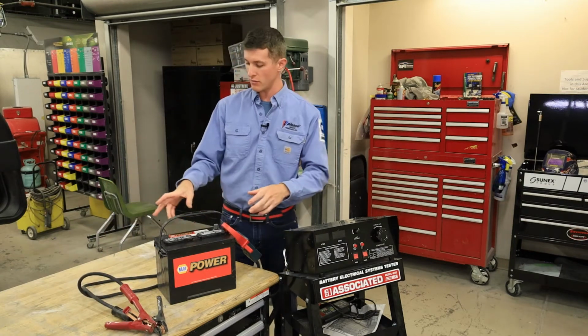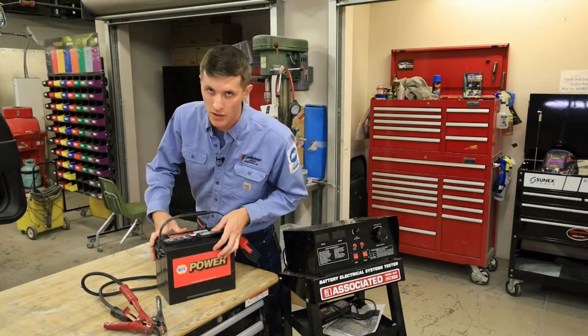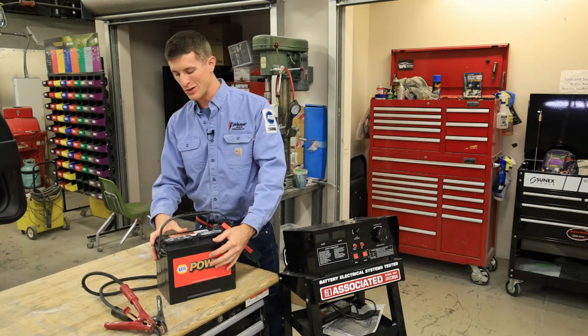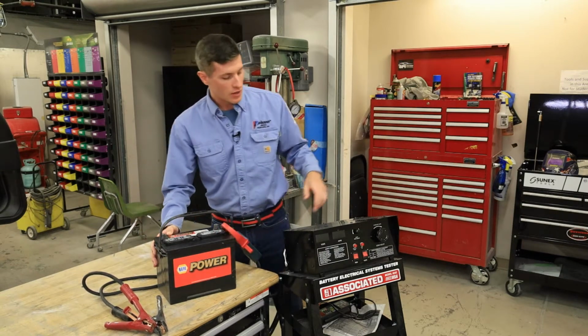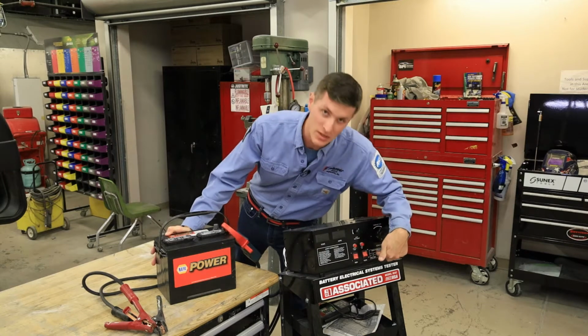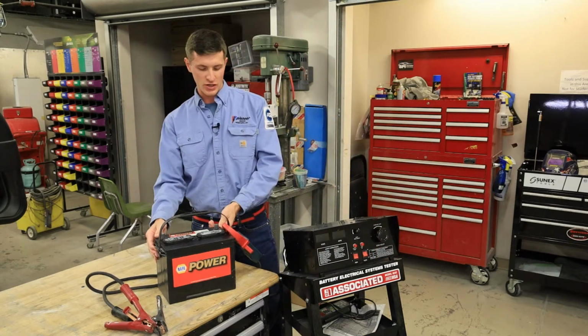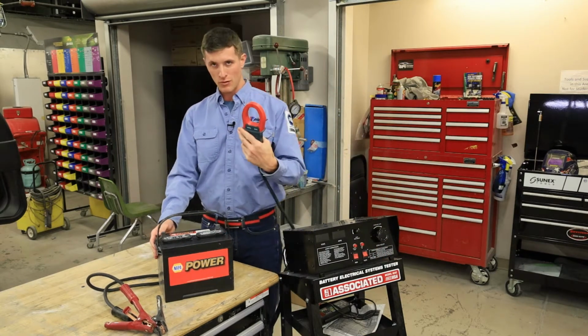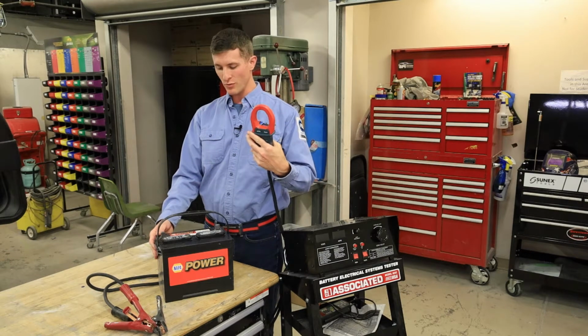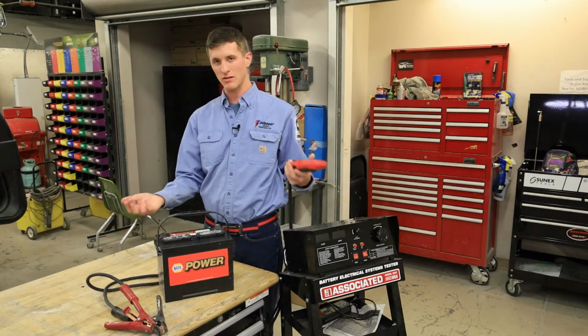Basically, we need a clean, fully charged battery. You cannot test a partially dead battery. You need the temperature compensation chart on the front of this machine, and you need to remember where to put the current probe.